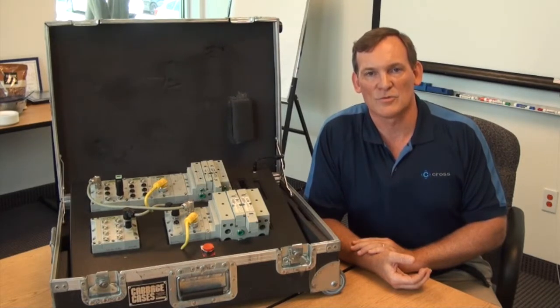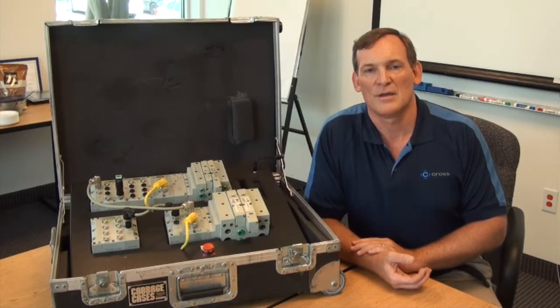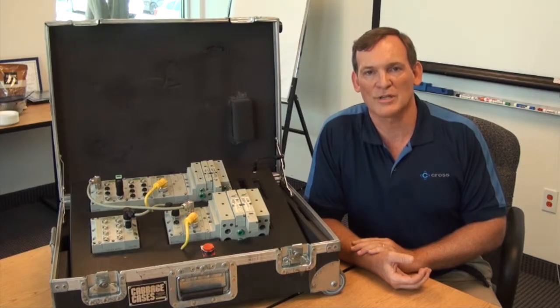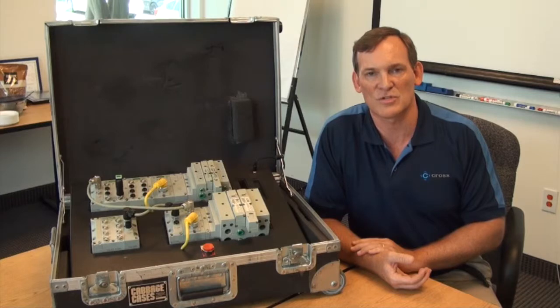An optional module that is available to the user is the ARM, or auto recovery module. This device uses flash memory to store all node parameters and I.O. settings. Within a few seconds after power-up, this device polls all connected modules and checks to ensure that all parameters match what has previously been stored.